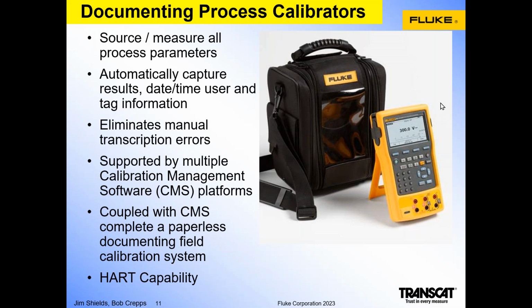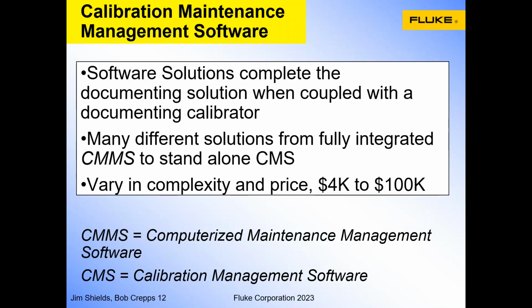In the case of most of these documenting process calibrators, they would have the HART communication functionality on board, in the event that the device that's being calibrated requires adjustment using HART communication protocol. Calibration management software, coupled with a calibrator, completes the documenting solution. There are a variety of different types of applications. CMS is what we call calibration management software, but there's also CMMS, which is computerized maintenance management software, with which these devices can also communicate.